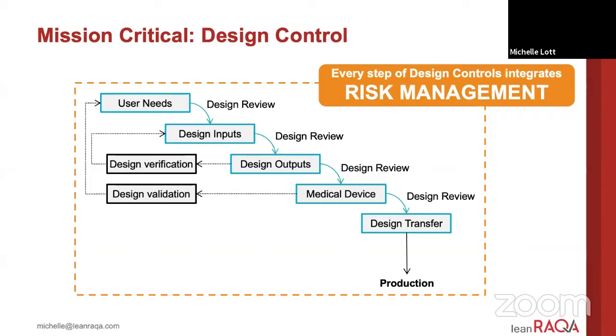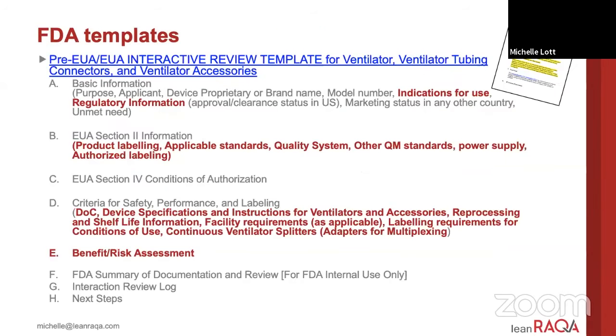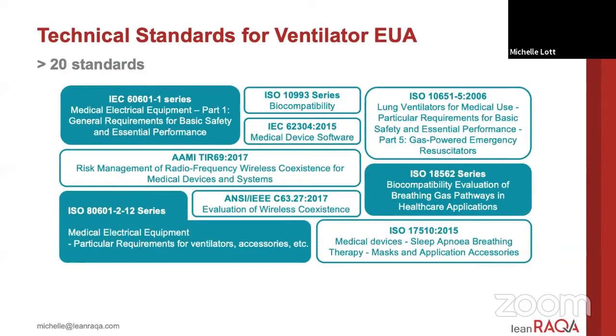The FDA has a whole formal process for how to design and document design controls, and the most important thing is that risk management is integrated the entire way. This even means during the emergency use authorization — if you look at the table of contents for the EUA, several of the elements, which I've highlighted here in red, are direct outputs of the design and development and risk management process. So you really can't cut these corners. And in the ventilator EUA, there are over 20 technical standards from a variety of families that are cross-cutting and touch almost every aspect of your product design.